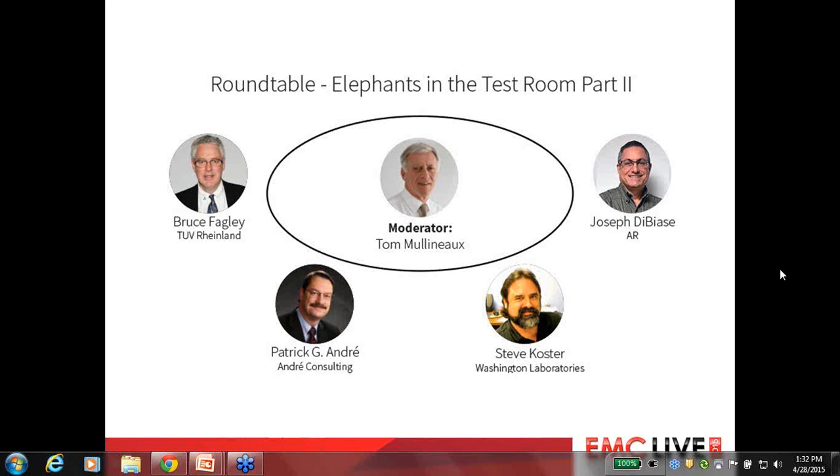There is a certain amount of irony in the fact that an EMC test facility is denied accreditation if the facility does not offer OATS testing. Yet it was confirmed during the last EMC Live event that there is an enormous disparity in inter-site OATS measurements. This begs the question as to why such a reverence is given to the OATS test site and why they are used as the basis of any type of reference at all. Can the ISO 17025 department charged with covering EMC laboratories not work with the EMC industry to improve OATS measurement consistency? Now let me start with the detraction.